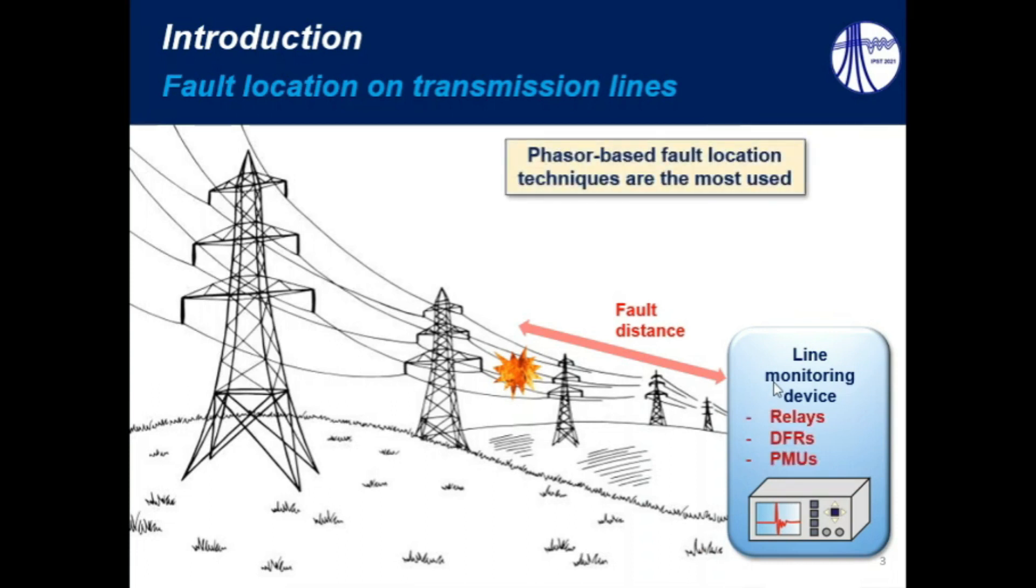But in this context, phasor-based fault location techniques are the most used, and these techniques can be applied considering phasor estimations taken from relays, externally estimated from instantaneous values obtained from DFRs, for instance, or even taken from PMUs.